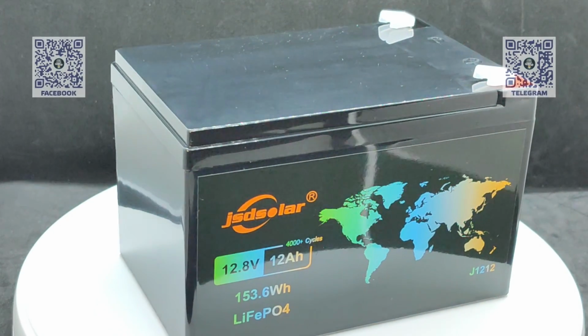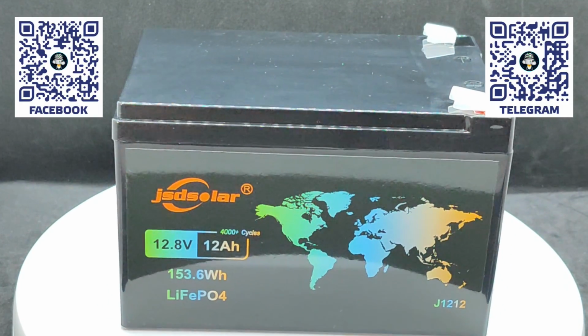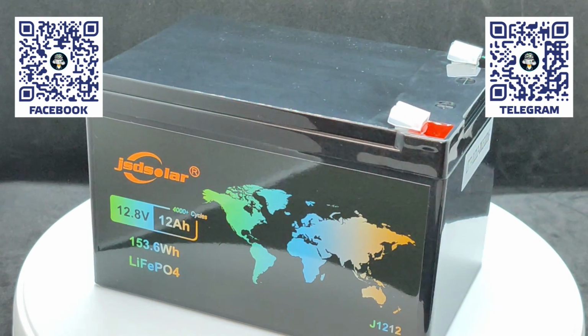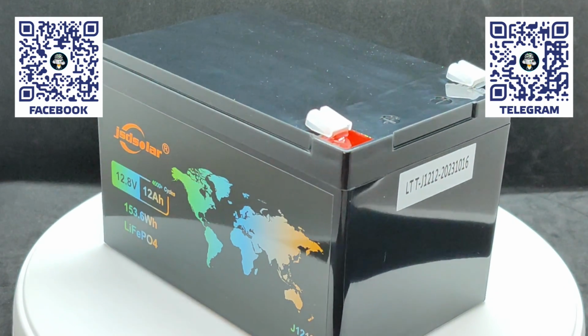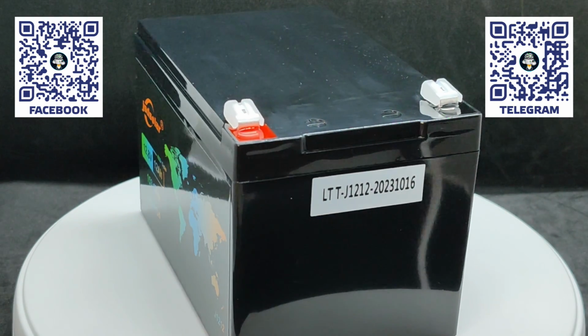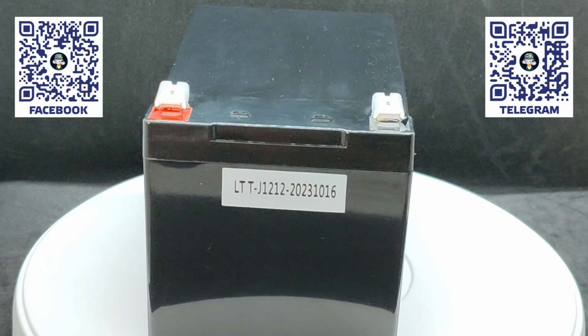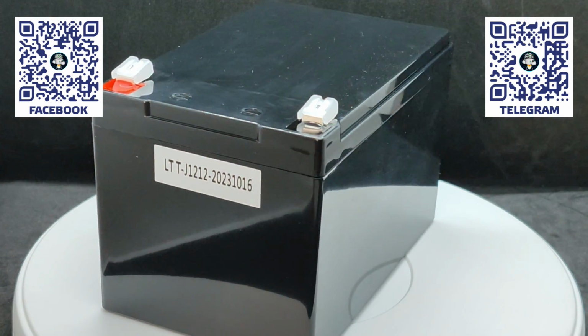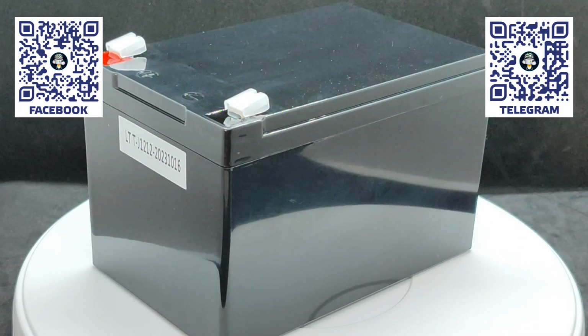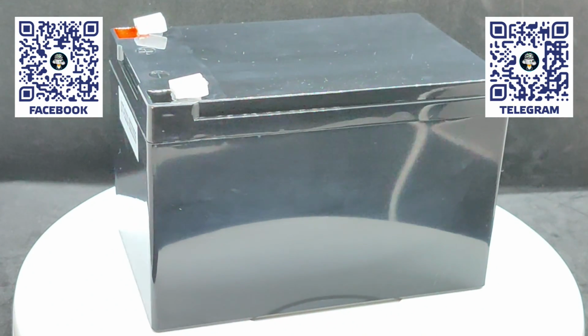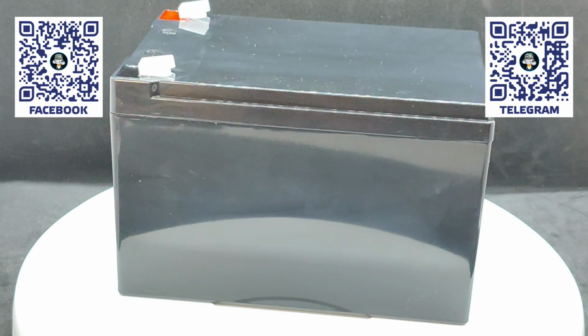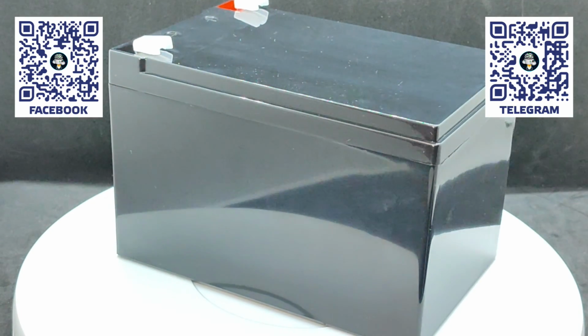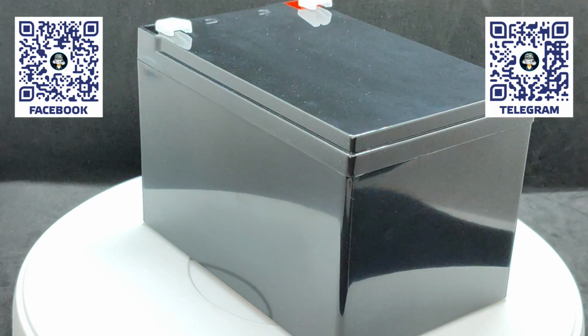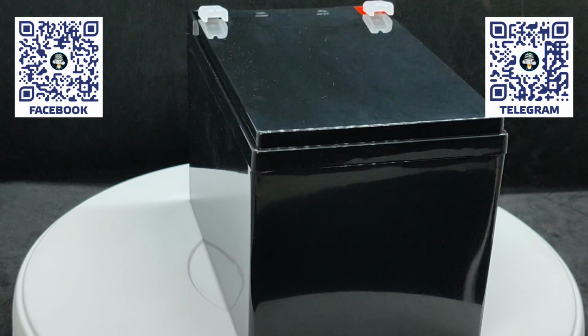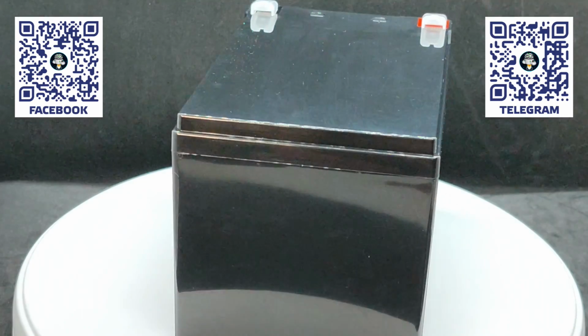For its price, especially considering the sale, and it cost me $37, I consider it an excellent option with an honest capacity. However, it's important to understand that when used in uninterruptible power supplies, the capacity will be less due to the buffer mode of operation, but on the other hand, there will be more charge-discharge cycles. When used with uninterruptible power supplies, where you can adjust the battery operation parameters, for example, with a universal DC UPS, a link to its review you will find in the description, you can set a higher voltage. 13.6 or even 13.7 volts, which is acceptable for such a battery and gives a slight advantage in capacity.